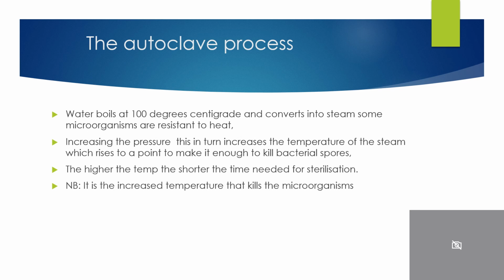So what takes place? In the autoclave process, we have water boiling at 100 degrees centigrade and it converts into steam. Some microorganisms, however, are resistant to heat. Increasing the pressure, this in turn increases the temperature of the steam, which rises to a point to make it enough to kill bacterial spores. The higher the temperature, the shorter the time needed for sterilisation. And please notice it is the increased temperature that kills the microorganisms.